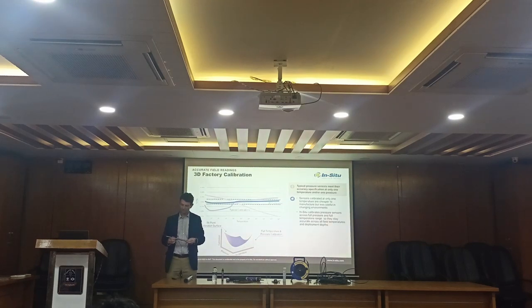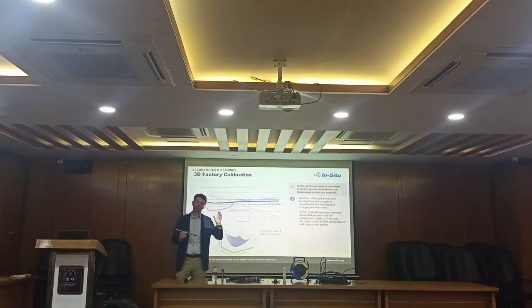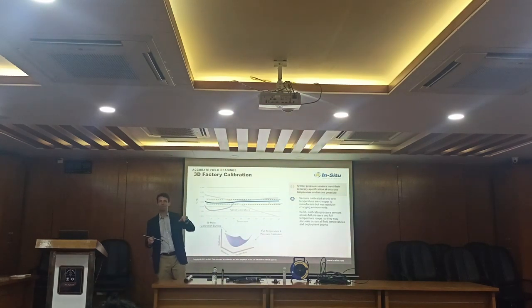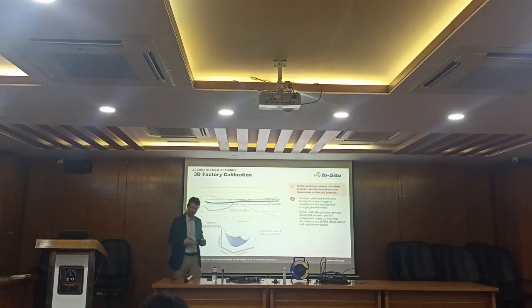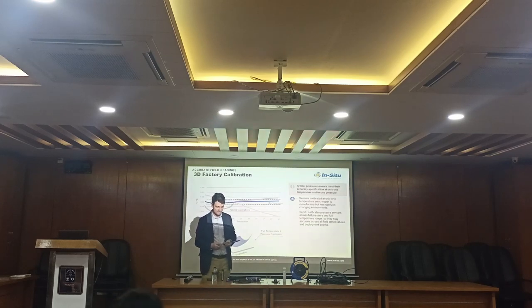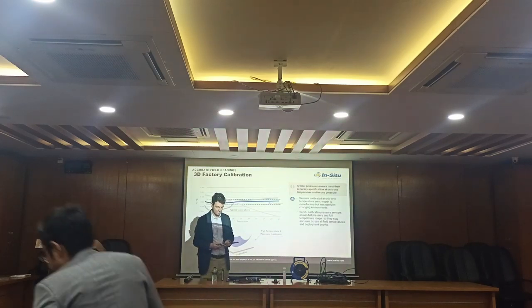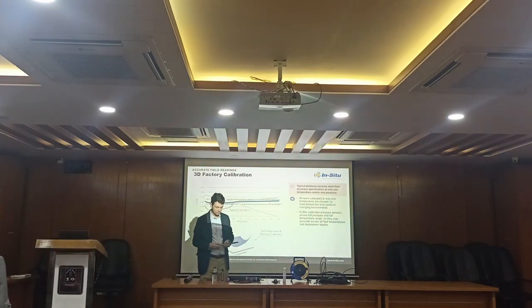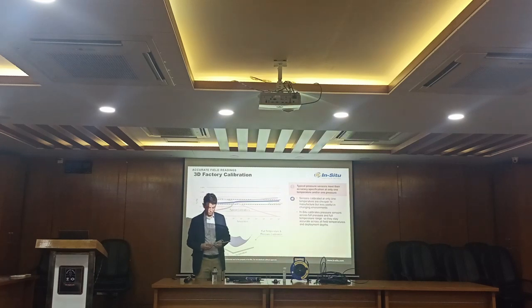And so how you actually determine how accurate they may be is based on the percentage of what's called full scale, FS. That's what this right here, FS, means. So this full scale is the range of this pressure sensor. The only way I can tell the range of this is by reading what it is, and I should remember because I've been using this one.